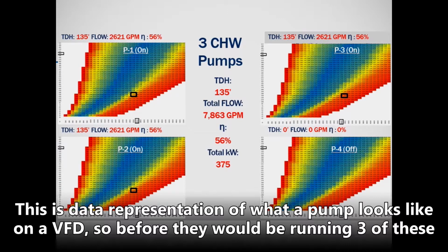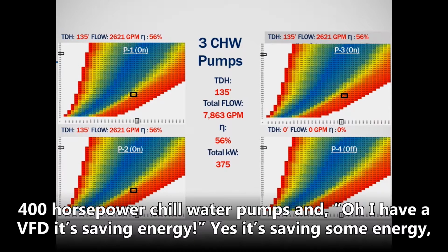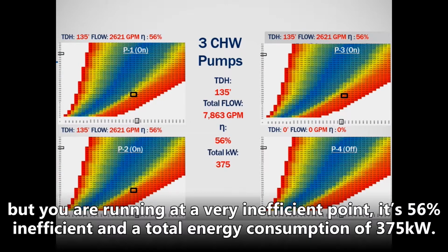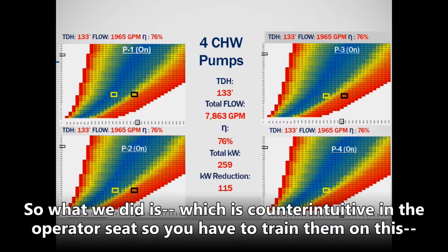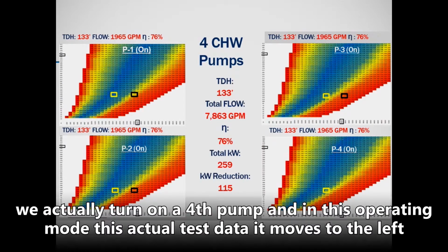So before, they'd be running 3 of these 400 horsepower chilled water pumps, and the common thought is, oh, I have a VFD, it's saving energy. Yes, it's saving some energy, but you're running at a very inefficient point. It's 56% efficient, and total energy consumption is 375 kW. So what we did, which is counterintuitive to operators, so you got to train on this, is we actually turn on a 4th pump in this operating mode.